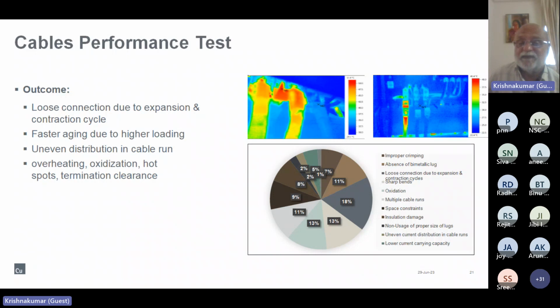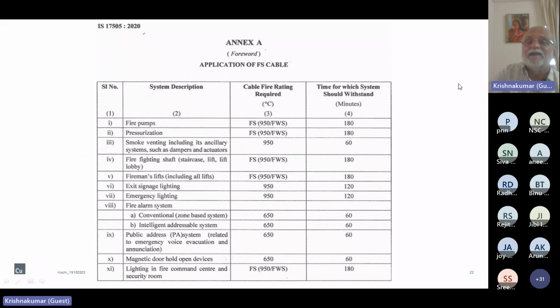I told you, up to 16 square mm, aluminum cables should not be used, because we made some thermographic studies where we found that when aluminum cables are terminated, over a period of time the tightness of the terminations gets loose, because they have a different coefficient of expansion. That loose contact will lead to heating up, undue heating, overheating, oxidization, and then result in fires. Okay, this has happened.